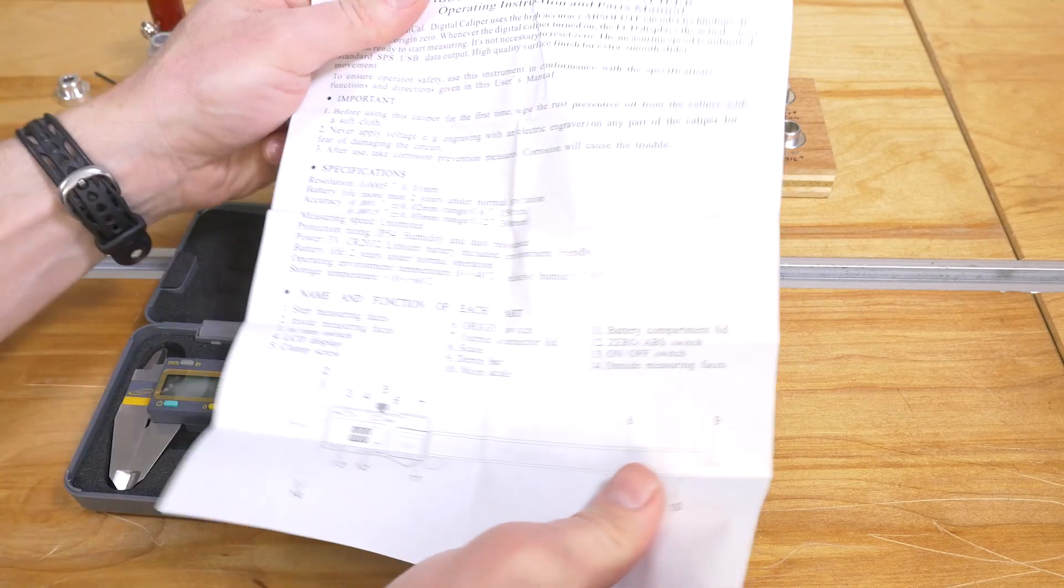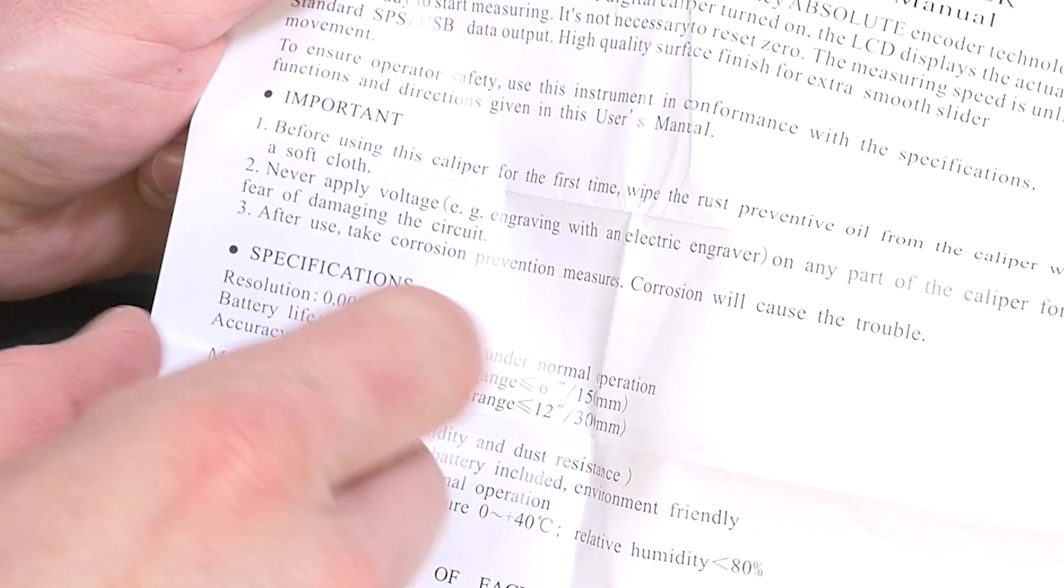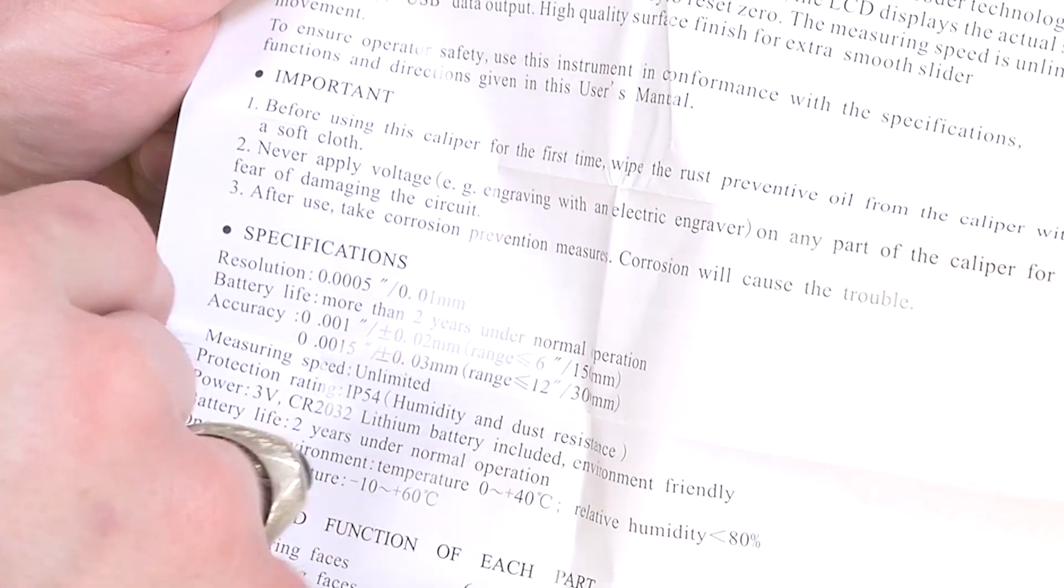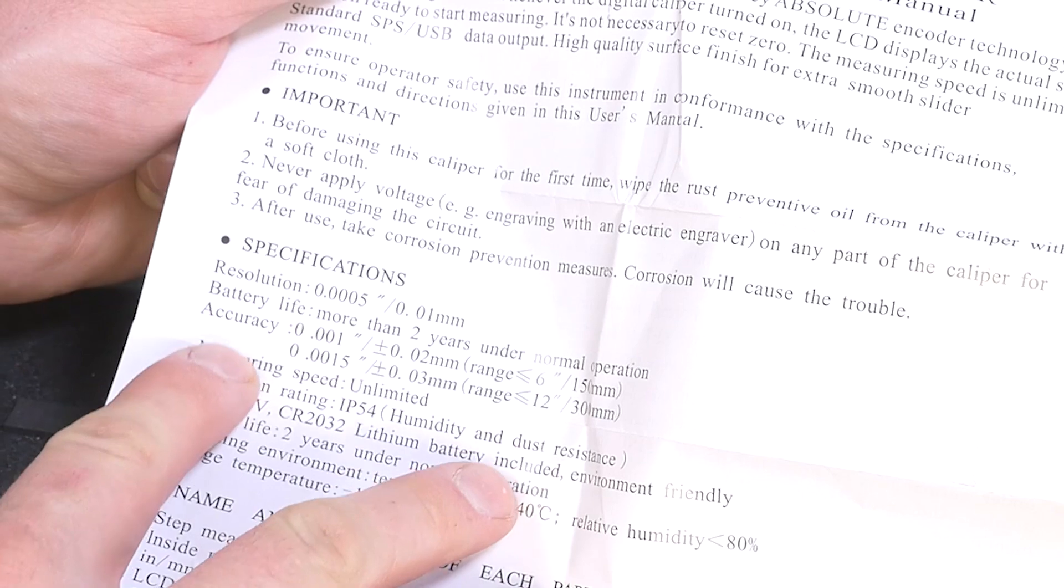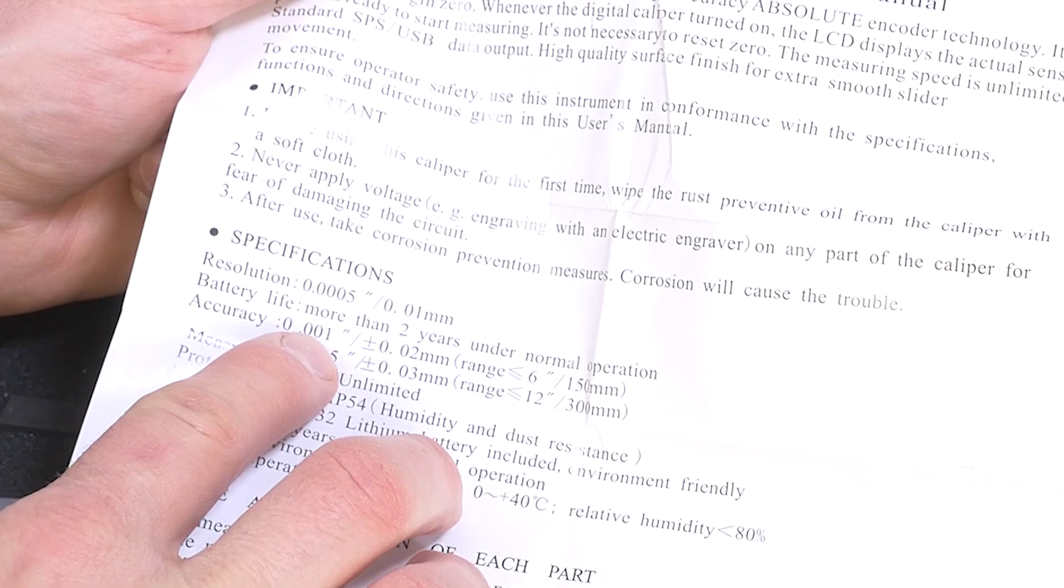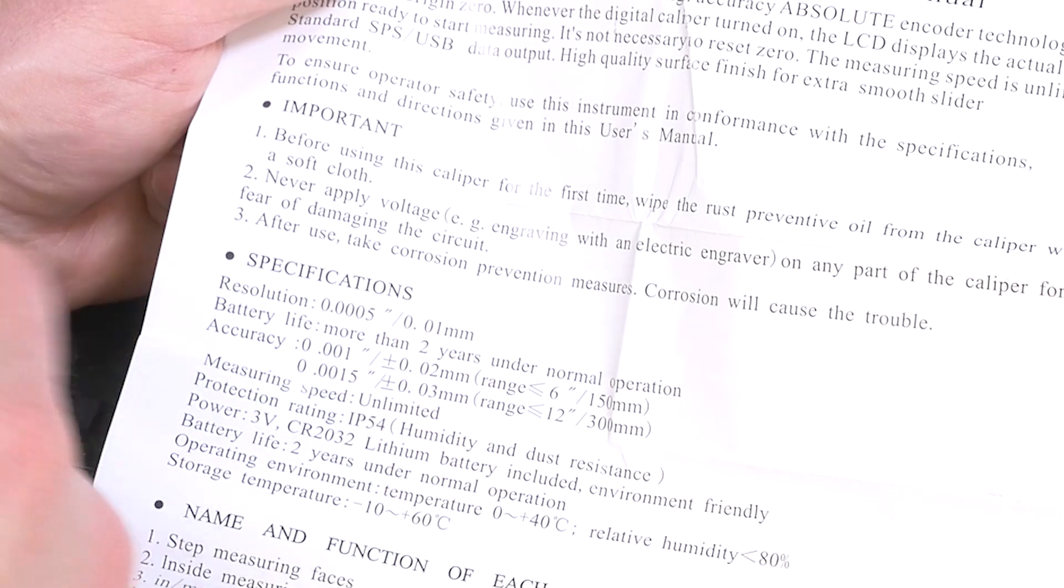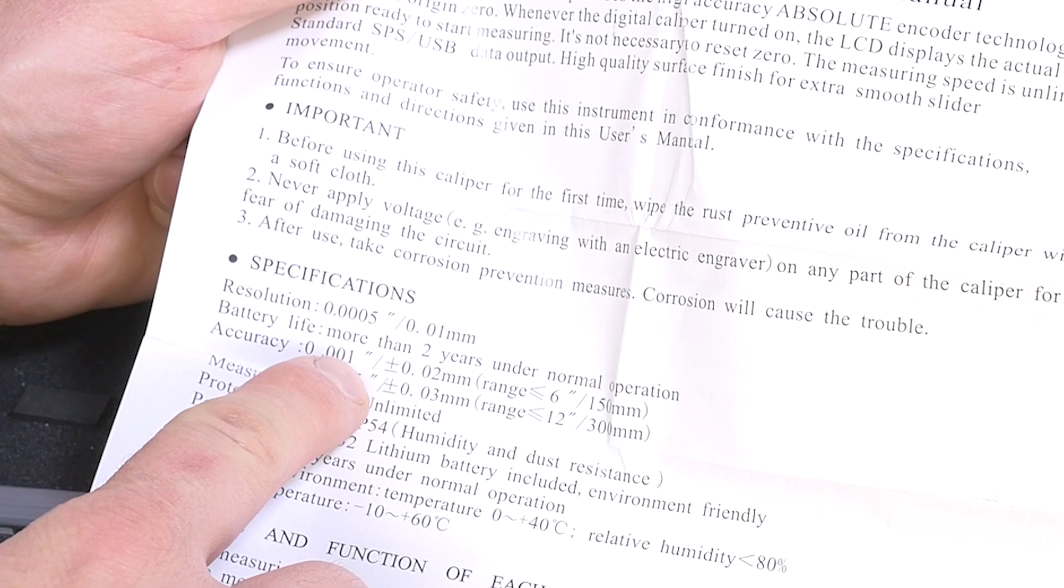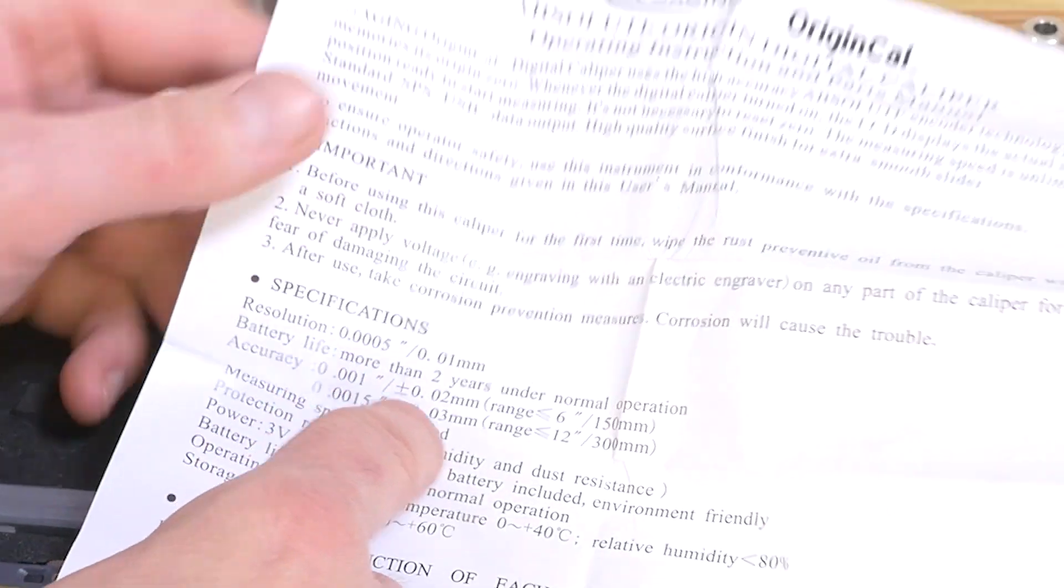We've got the instruction sheet here, so we can see we have a resolution of a half of a thousandth of an inch. That means that's the minimum distance it's capable of measuring when you open and close the jaws. It says more than two years under normal operation for battery life, accuracy of one thousandth of an inch. That means relative to some fixed known value, if we had a block of aluminum that was an inch exactly and we measured it, it should be within a thousandth of that inch reference point. And when we move it, we can detect up to a half thousandth of an inch of movement.